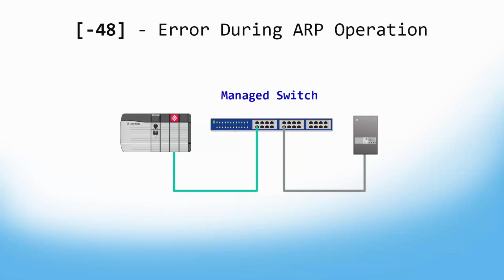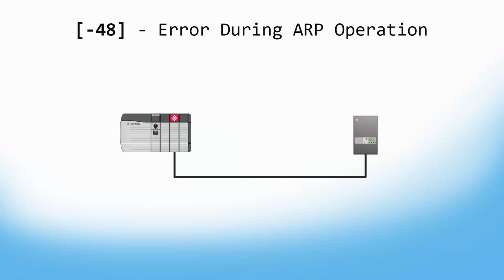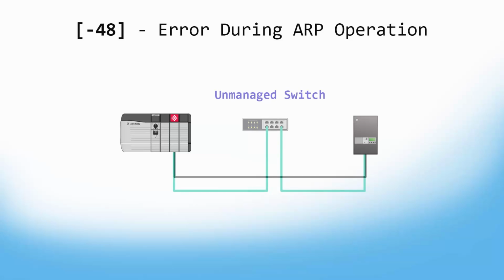For testing purposes, try to make a direct connection from the module to the target device. If that's not an option, you can try going through an unmanaged switch. If you're able to establish communication, then you know that you need to configure your managed switch.